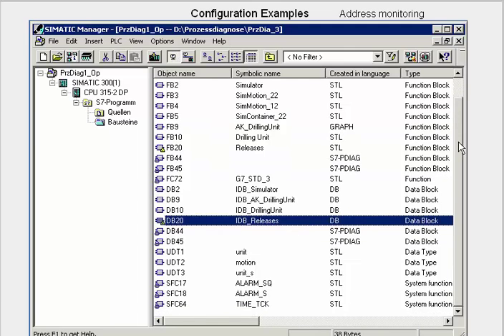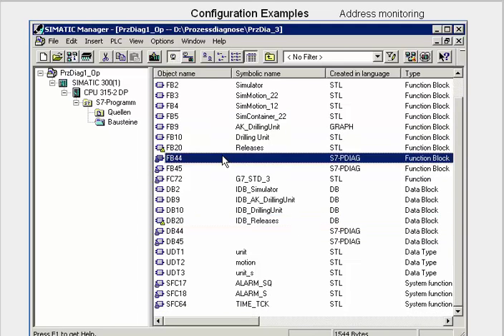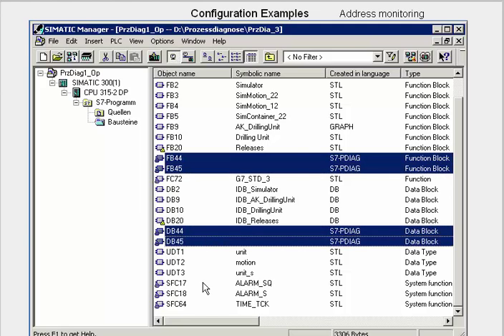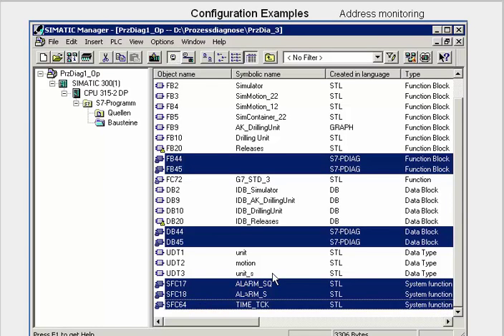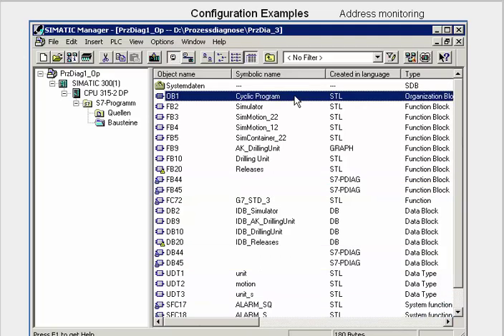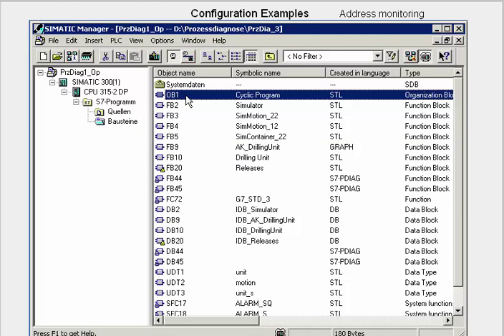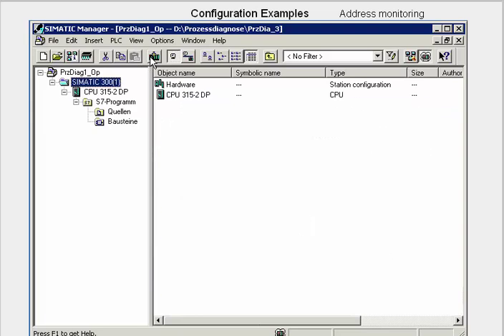In the block overview of the SIMATIC manager, we see the newly generated monitoring blocks and the required system functions. Then we open OB1 and insert the code lines for calling the monitoring blocks. We save OB1 and close the block editor. Now we load the Step 7 project into the CPU.